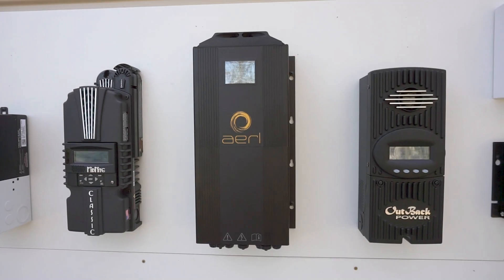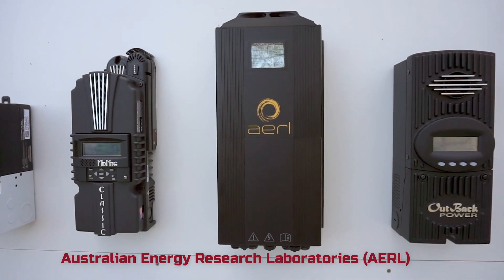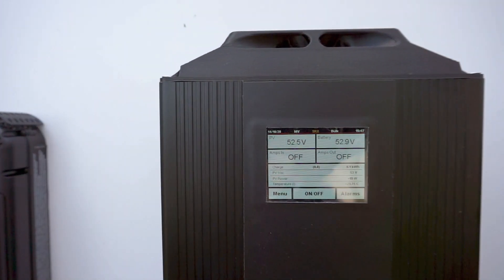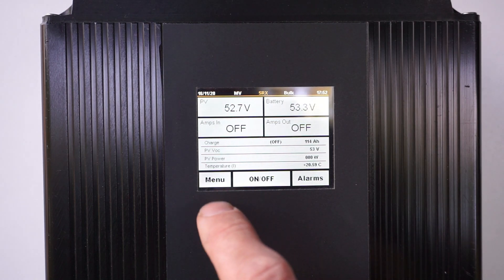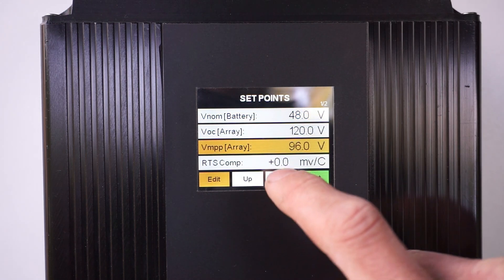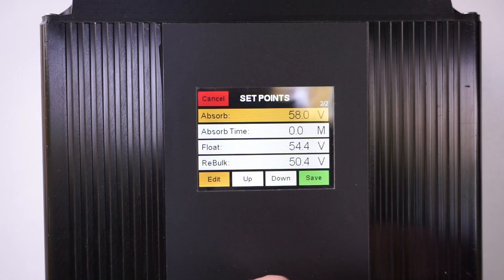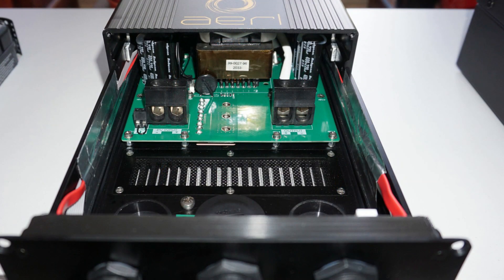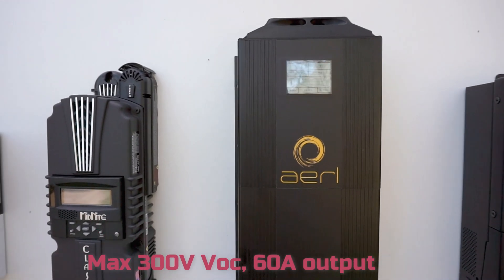Next we have the Coolmax SRX from AERL. This is Australian designed and manufactured, and is the newest of all the charge controllers, released in 2019. AERL has actually been around since 1985 and this company invented the MPPT. One of the biggest highlights of the Coolmax SRX is the color touchscreen display — it's really easy to use and set up all the parameters. It's a very large unit with a huge heat sink in the back made from a large piece of extruded aluminium, and it also has an inbuilt fan. This has a maximum VOC of 300 volts, the highest of this group, and a 60 amp charge current.